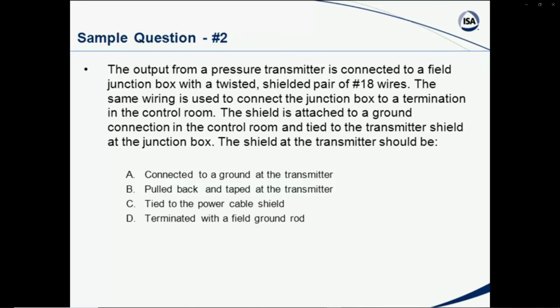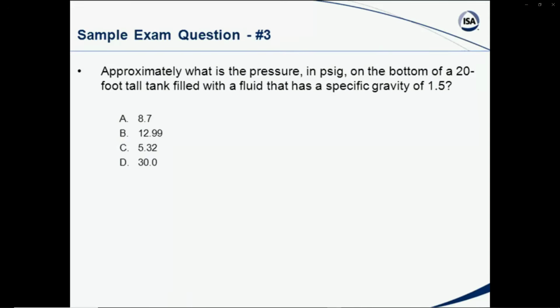Again, that's one that you should read. You should take it into account and read what it's saying. You may have a reference to look that up in. You may just know this. You may understand this. You just need to take your time. You have 6 minutes per problem. Some of these will be low-hanging fruit, and you can just zap it out real quick, and other times maybe a little bit more difficult. In this particular case, the answer would be pulled back and taped at the transmitter. You don't want to ground the signal cable at both ends because you might have ground loops set up. We had that on one of the slides, and it would be an example of the type of question that could be asked.